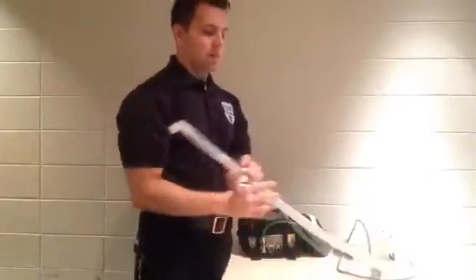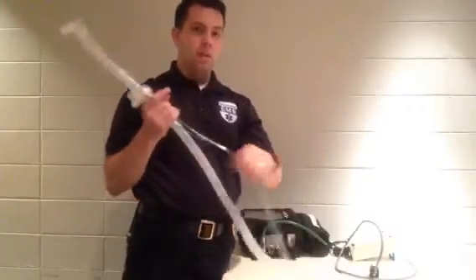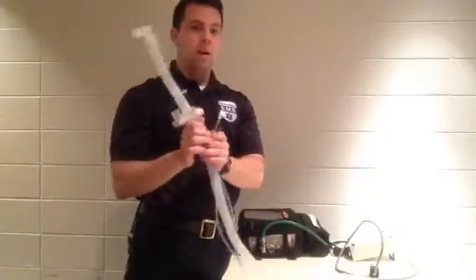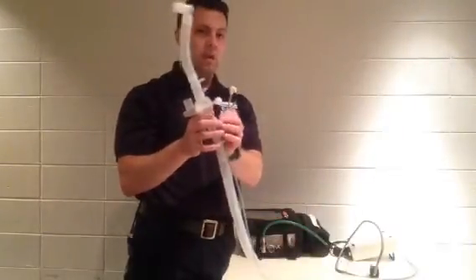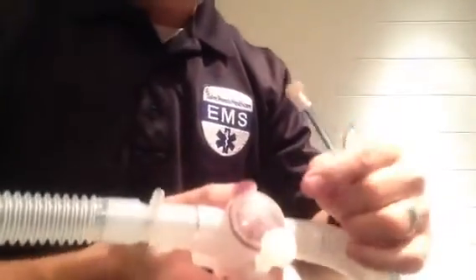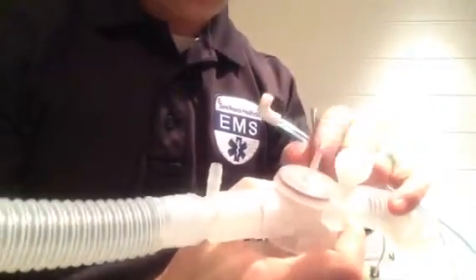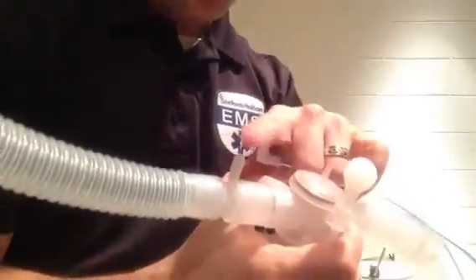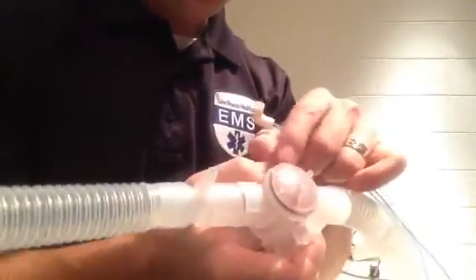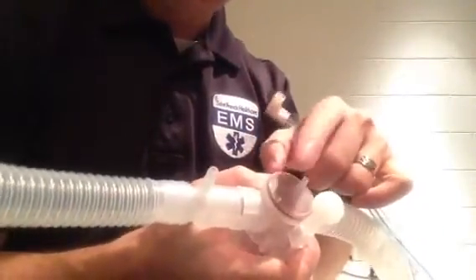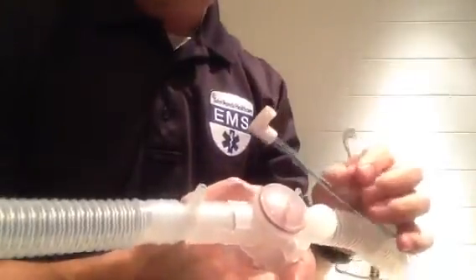The first thing that you're going to need to do is these extra monitoring lines are not attached to the main vent circuit. They need to be attached. When we bring them close, you've got a couple different attachment points that you see. You've got this guy right here, and you've got this guy right here. Clearly you see the actual membrane here. That's your valve. That's your exhalation valve.